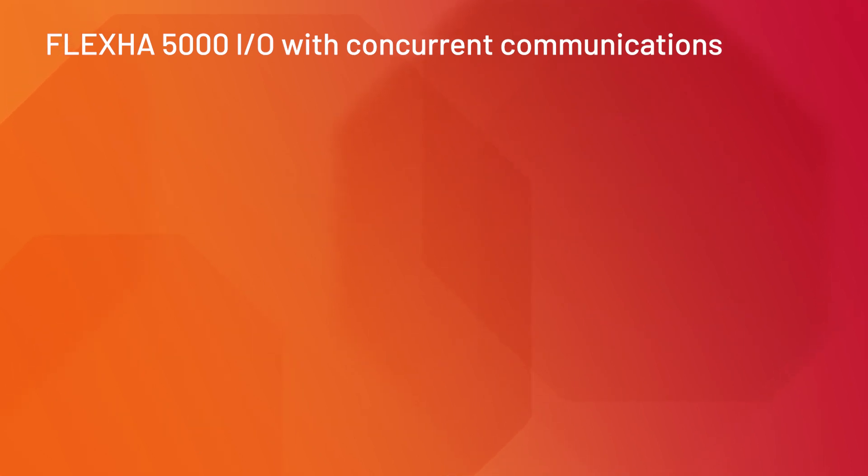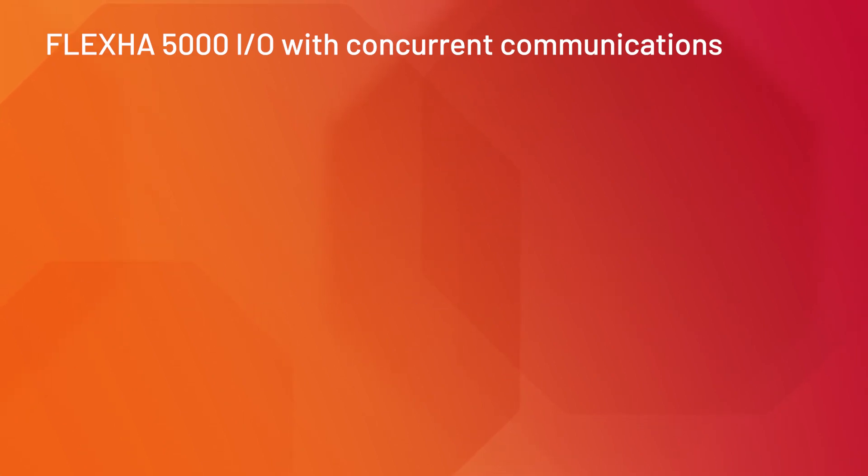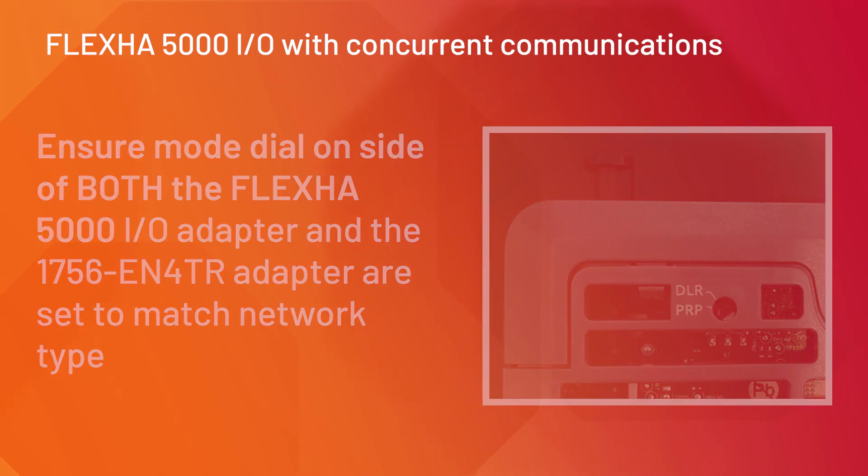For the hardware configuration, determine whether a DLR or PRP network will be used. Next, ensure that the mode dials on the side of the FlexHA 5000 I/O adapter and the 1756-EN4TR adapter are set to match the network type.